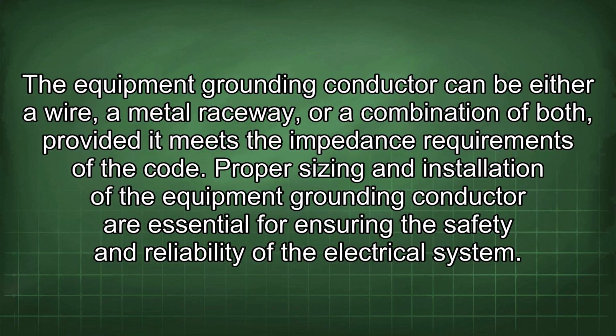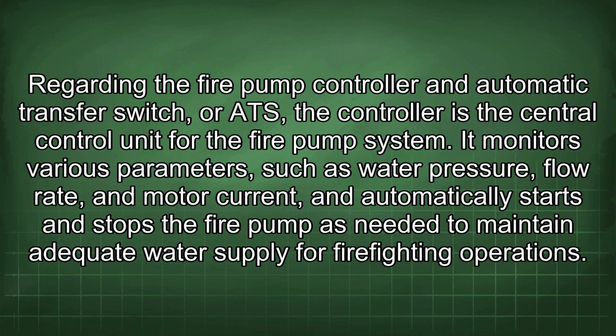The equipment grounding conductor can be either wire, a metal raceway, or a combination of both, provided it meets the impedance requirements of the code. Proper sizing and installation of the equipment grounding conductor are essential for ensuring the safety and reliability of the electrical system. Regarding the fire pump controller and automatic transfer switch, or ATS, the controller is the central control unit for the fire pump system. It monitors various parameters such as water pressure, flow rate, and motor current, and automatically starts and stops the fire pump as needed to maintain adequate water supply for firefighting operations.